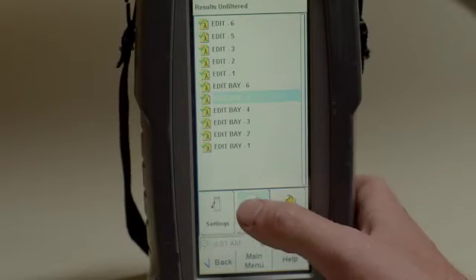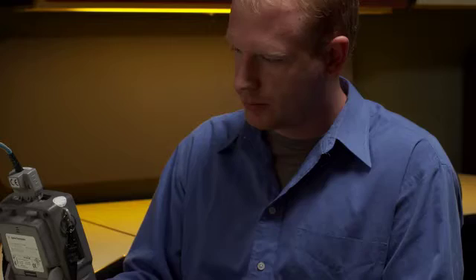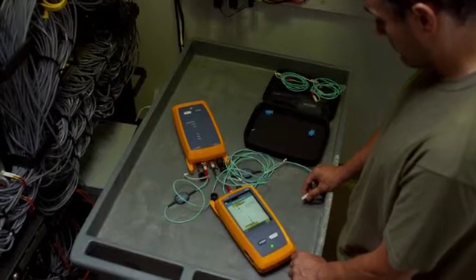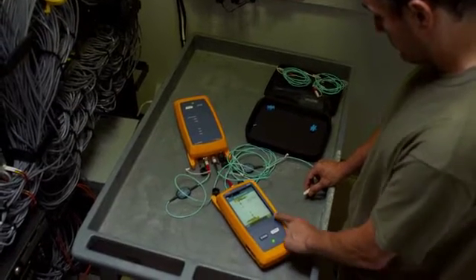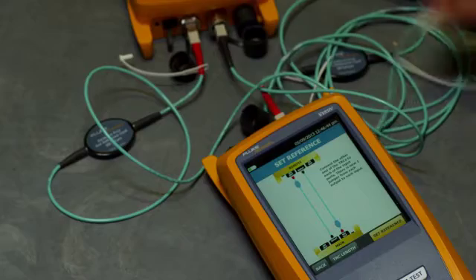For example, one of the most common calls we get in tech support is about negative fiber loss measurements. They're caused by setting the reference incorrectly, which is easy to do. And when it happens, it means all the fibers have to be retested. But the Taptive user interface steps the user through the process, eliminating the problem. I am not going to get those calls from Versiv users.